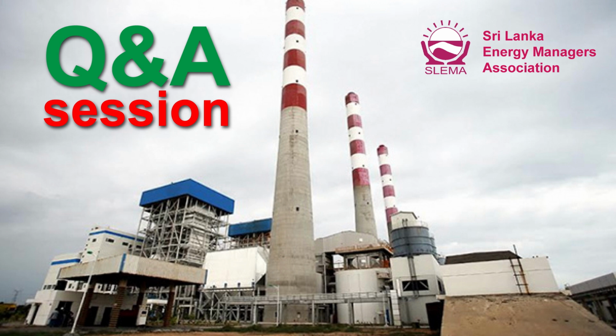Yes, the last one. Isn't pump storage supposed to peak the demand dispatch? How could it be supporting a frequency control issue like what happened in the recent Norochcholai breakdown? Now, it's not necessarily that it will stop the Norochcholai tripping, of course, not a breakdown, it's a tripping.